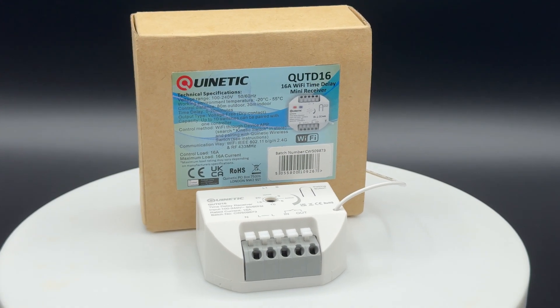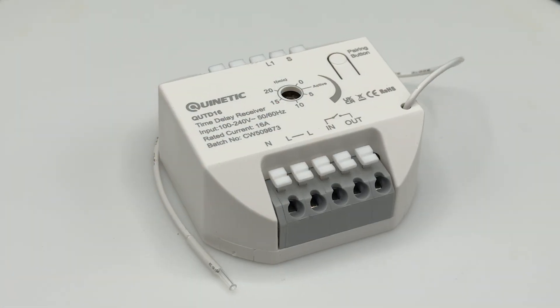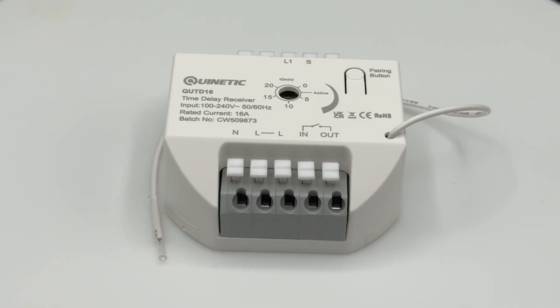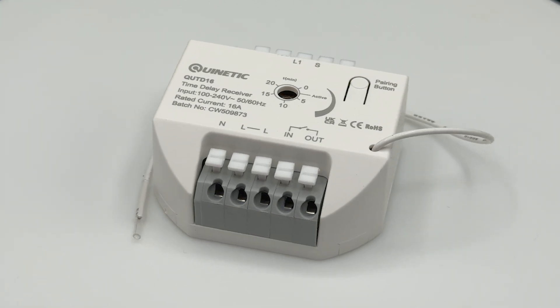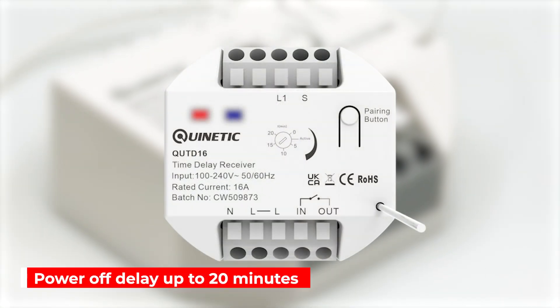It works with both Quinetic and traditional switches for dual or multiple control, allowing easy two-way switching between traditional and Quinetic switches. Its primary feature is an off-delay timer which is set and adjusted by a rotary knob that can alter the power off delay for up to 20 minutes.